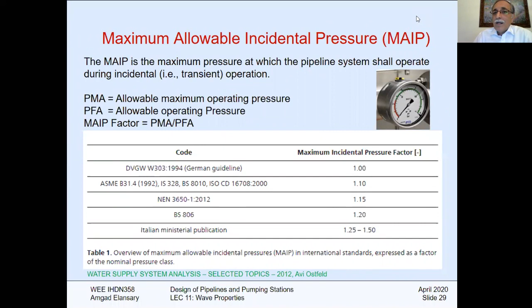On the NEN European standard, it will allow for 15%. On the BS, the British standard, 20%. On the Italian, they allow a range between 25% to 50%. What I'm going to do, I'm going to use 1. We're going to use the first one. I will not say to you why, but I'm going to use 1. I will not allow for maximum pressure or class rating of the pipe to exceed more than the same class rating, static plus transient. If I divide it over the class rating, which is the same, it will be 1. So this is the way we are going to use our design.